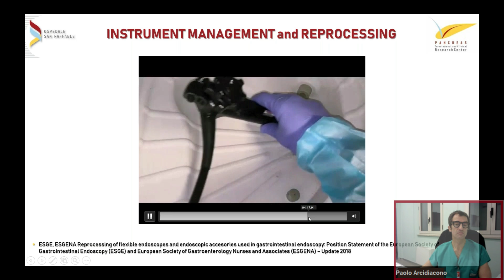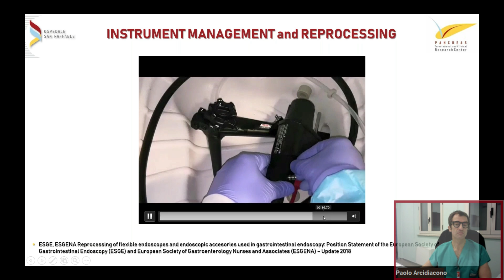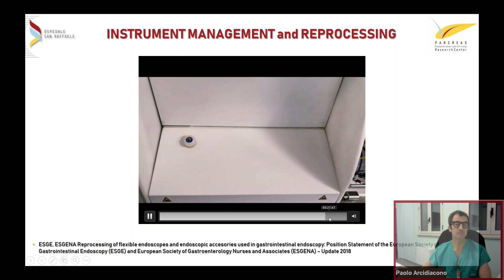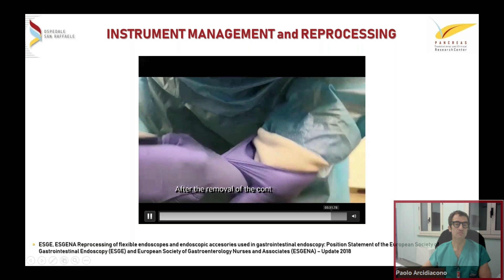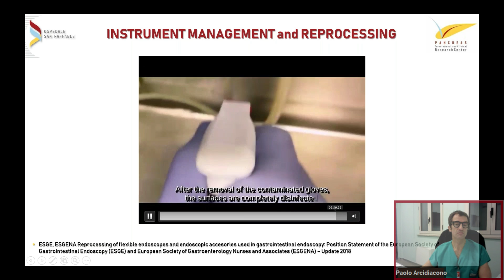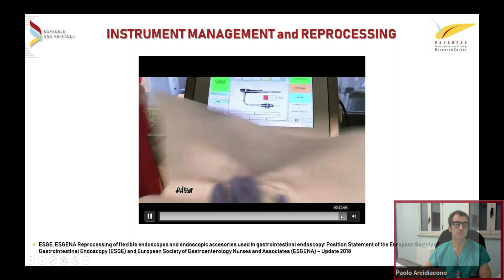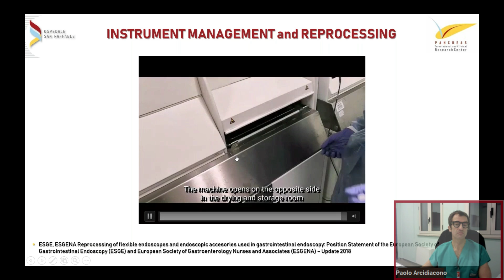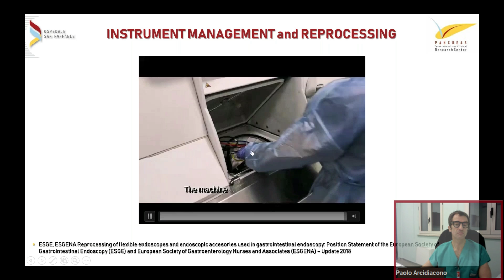and so this is plugged, and this comes into our washing machine. You see, we have a double lumen washing machine with the dirty part and the clean part. So at the end of this process of cleaning, you can see the machine is closing. At the end of this process of cleaning, the machine arrives at the end. And so on the other part, in the clean part of our washing area, there's the opening of the machine, and the instrument is taken out from the machine by another nurse who puts the instrument on this area.